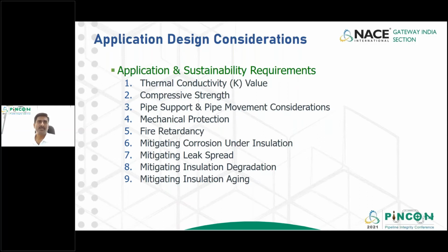Mitigating corrosion under insulation. Mitigating the leak spread: in case of a leak, it must be confined within a single joint. Mitigating insulation degradation by using a durable and rugged weathering jacket. Mitigating insulation aging, preventing aging of insulation for its design service life.